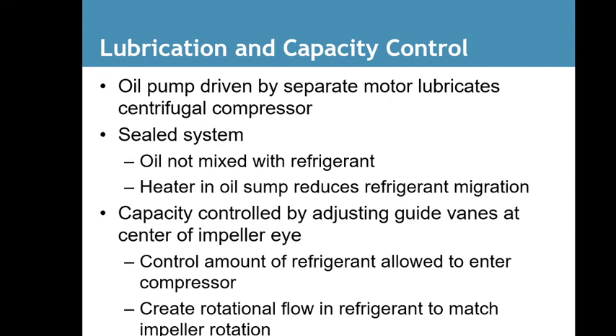Lubrication and oil capacity control. Oil pumps are driven by separate motors that lubricate centrifugal compressors. What's good about this is you could start the oil pump before the compressor starts. That way it's pre-lubed, so you don't take a chance of it starting up dry like the car that you drive. There's no oil movement until the engine is started, which gives you a chance, if a car is sitting for a while, it could have lost a lot of the oil that lubricates the inside of the engine. Sealed systems, oil does not mix with refrigerant.